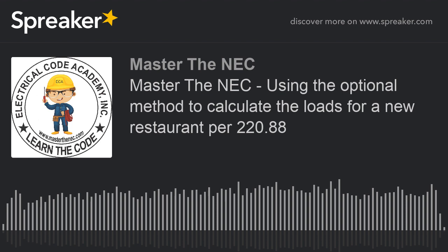Why? Because those feeders, there's more than one, and they're serving other loads, so those feeders are not serving the total load of the restaurant. Okay, makes sense? So what would you size them? Well, you would size the panels that they're maybe feeding based on part 3 for whatever the loads that are in that panel, and subsequently that's going to how you size the feeder conductors, right? Based on the load that's in that panel, the load being served.